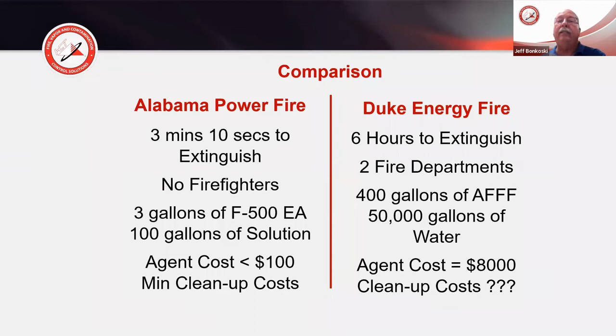But now we look at this other incident that happened with a transformer. It took 6 hours to extinguish, with 2 departments, 400 gallons of AFFF foam, and 50,000 gallons of water. The agent cost was $8,000. And the cleanup cost was in the millions because, again, the containment area where that transformer was located wasn't able to hold 50,000 gallons of water and solution. And again, we have those forever chemicals, the PFOAs and PFOSs, causing environmental impact. And they do not work on 3-dimensional fires.